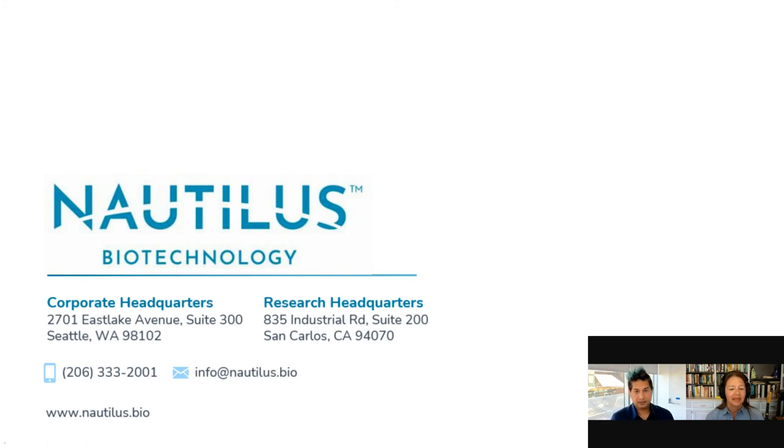All right. Next question: how does sample multiplexing work? How many can be run at once? Yeah, that's a great question. I didn't show the architecture of the flow cells, but the flow cells are arranged such that the set of flow cells that are inserted into the instrument have 12 lanes. And so there's a natural way to multiplex 12 samples at once. We also are continuing to work on in-lane multiplexing to support even more multiplexing beyond that.